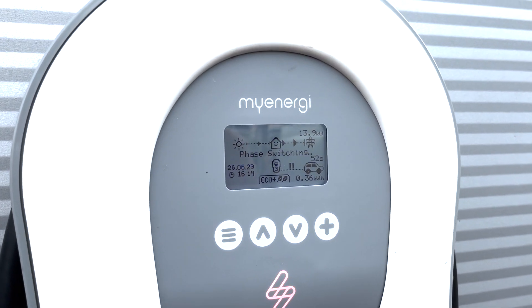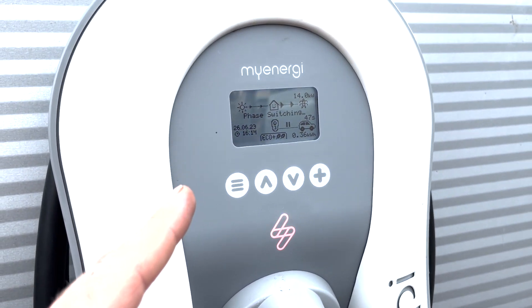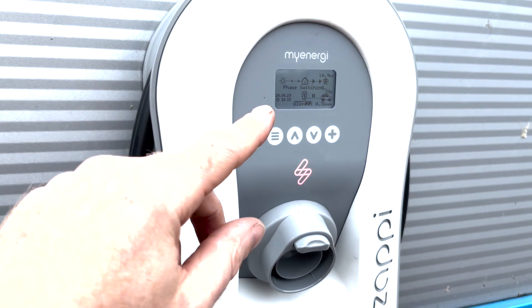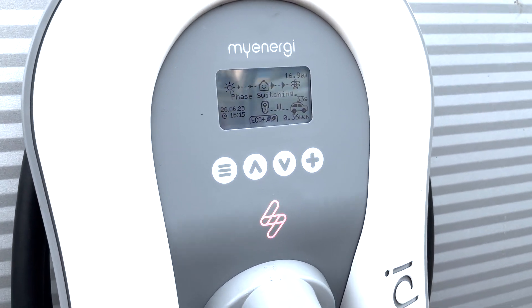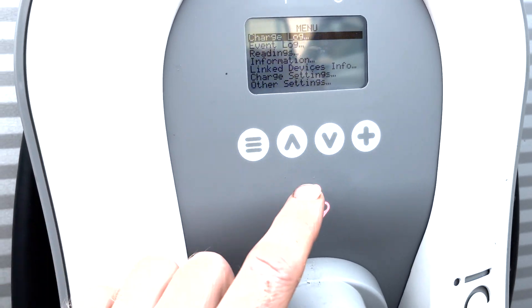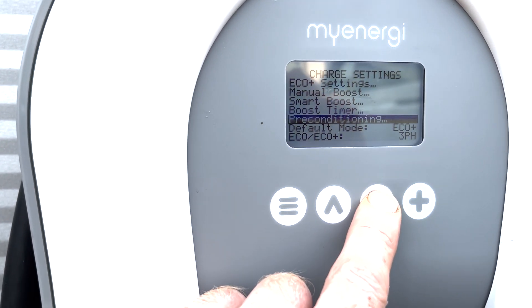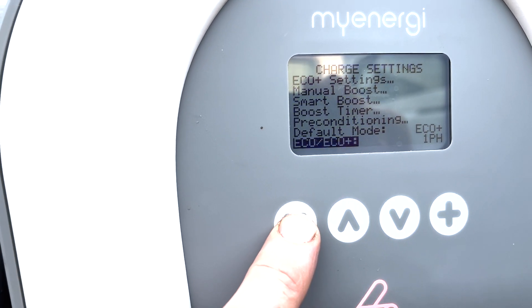In this video we're going to show you how to check your phases are correctly connected if you've got a three-phase Zappi, because your CT clamps need to be connected in the right order. This goes through two distribution boards and someone may have swapped the phases over somewhere, which means it can't regulate. What we can do is set the Zappi to trick it into thinking it's a single phase — I've set it to one-phase charging now.